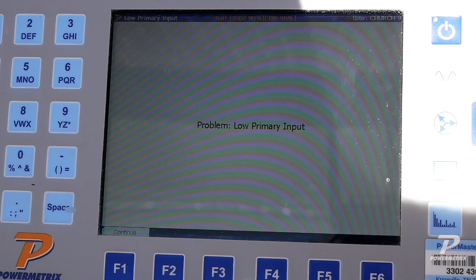Notice it started giving error messages. We've talked about this before. When it starts giving you one error message after another, that's usually indicative of no load. He was moving, repositioning stuff, so when he disconnected and moved it, the unit thought it had no load. So just remember, when you start getting cross phase, low primary input, polarity reversal, one after another, Danger Will Robinson, it's saying I don't have enough. That's what happened here when he disconnected and was repositioning it, so it didn't see enough load and gave those same error messages as if there wasn't enough load at the site.